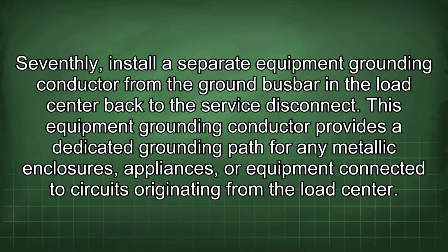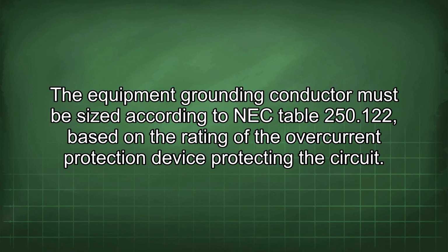Seventhly, install a separate equipment grounding conductor from the ground busbar in the load center back to the service disconnect. This equipment grounding conductor provides a dedicated grounding path for any metallic enclosures, appliances, or equipment connected to circuits originating from the load center. The equipment grounding conductor must be sized according to NEC table 250.122, based on the rating of the overcurrent protection device protecting the circuit.